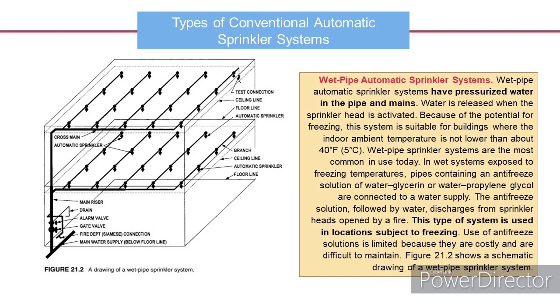Wet pipe automatic sprinkler systems have pressurized water in the pipe and mains. Water is released when the sprinkler head is activated. Because of the potential for freezing, this system is suitable for buildings where the indoor ambient temperature is not lower than about 40 degrees Fahrenheit, 5 degrees Celsius. Wet pipe sprinkler systems are the most common in use today.